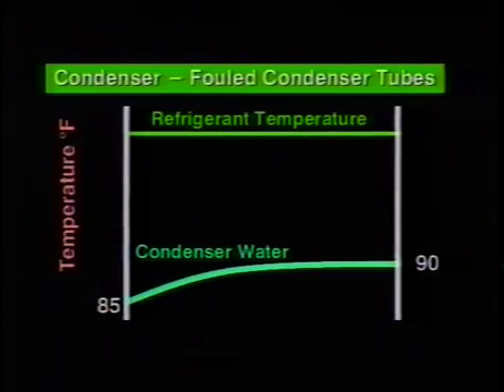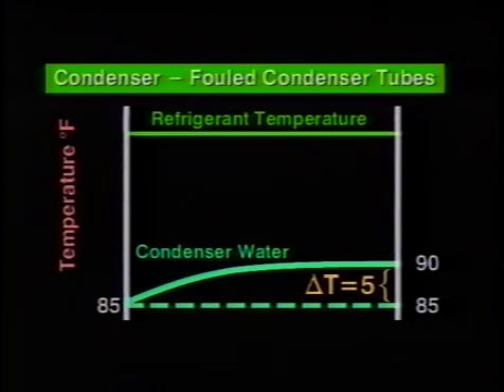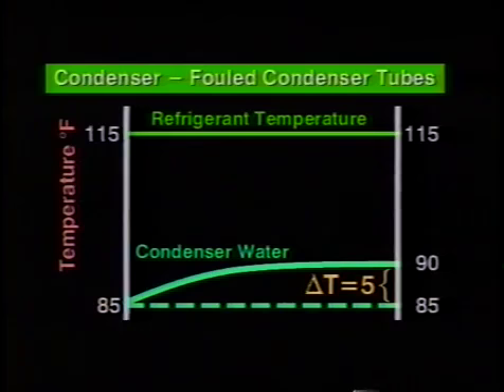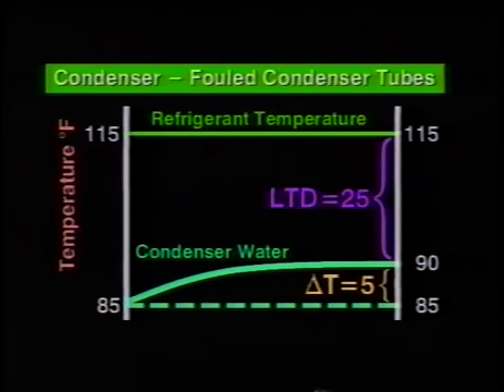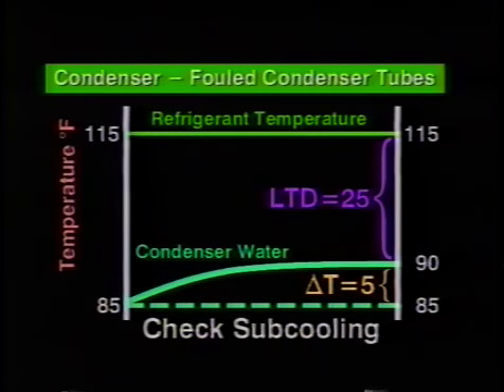Here, the capacity of the system is somewhat low, and we only have a 5-degree Fahrenheit delta T across the condenser. Our HCFC 22 refrigerant pressure is 243 psig, which is a saturated temperature of 115 degrees Fahrenheit. This gives us an LTD of 25 degrees, which indicates that our heat transfer is being impeded. These symptoms indicate that fouled condenser tubes would be a prime suspect, especially if the subcooling is lower than design.